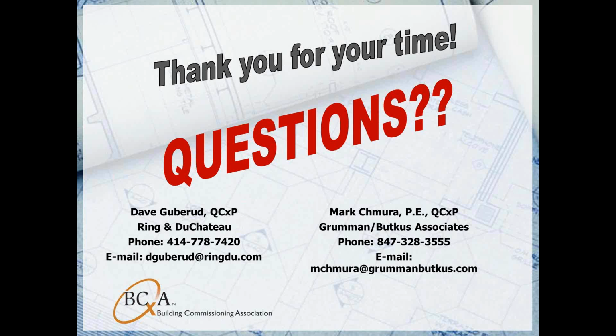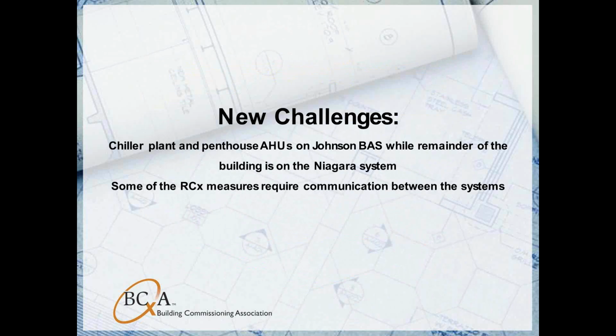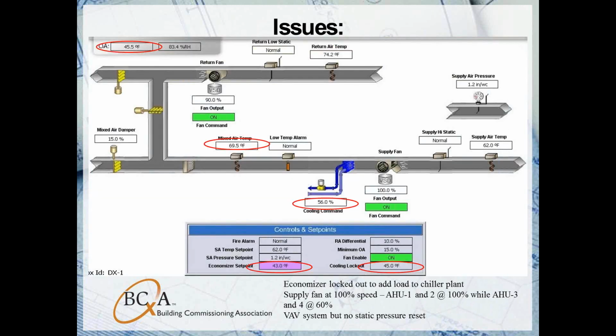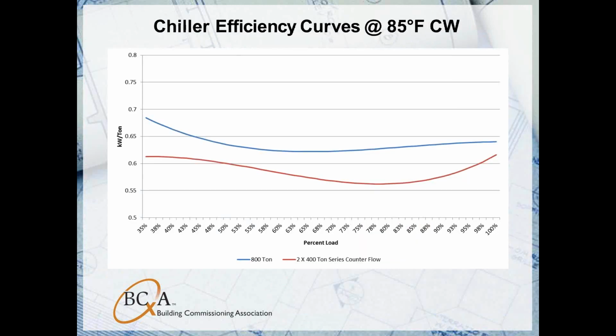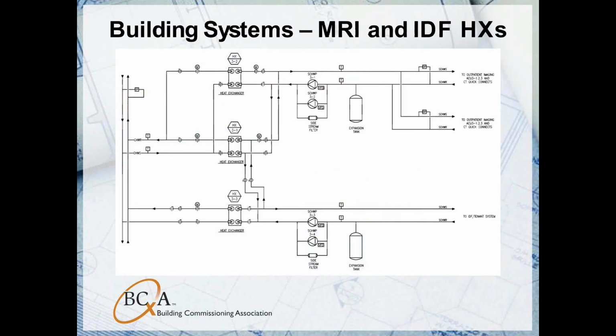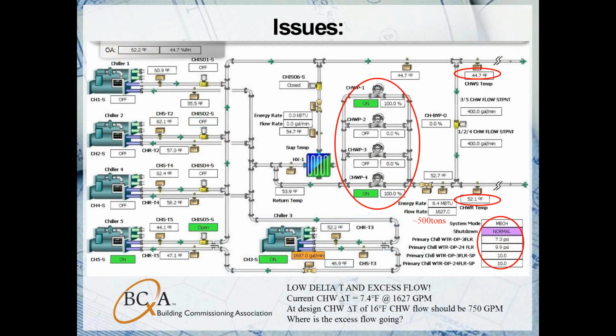The first question is, we did say that series counterflow is more efficient than using the single chillers in parallel. So why abandon the series counterflow? Well, the answer to that is typically you wouldn't want to. The issue with this plant is that they did have plans for future expansion in the MRI area, which would increase the load on the building. So the plant was sized with that in mind. Unfortunately, that never went forward, and they're left with a plant now that's oversized for the original intent.